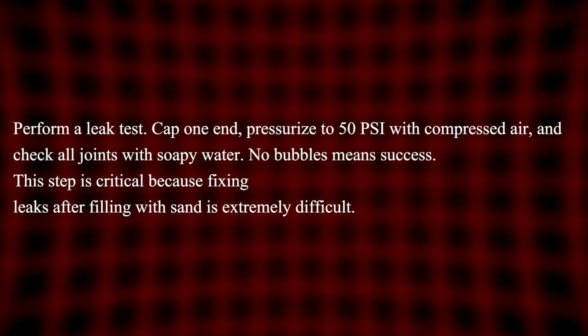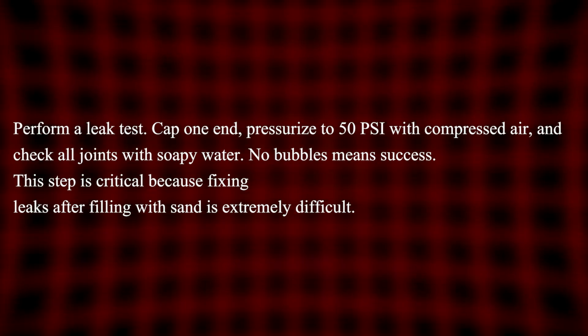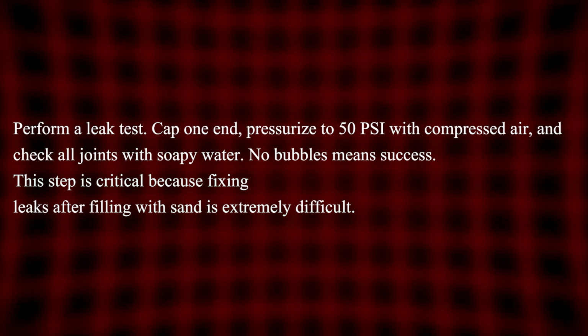Step 4. Perform a leak test. Cap one end, pressurize to 50 pounds per square inch with compressed air and check all joints with soapy water. No bubbles means success. This step is critical because fixing leaks after filling with sand is extremely difficult.